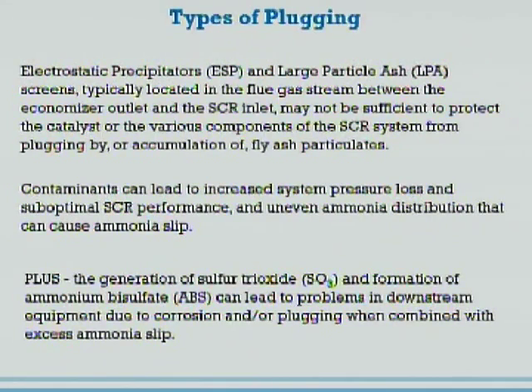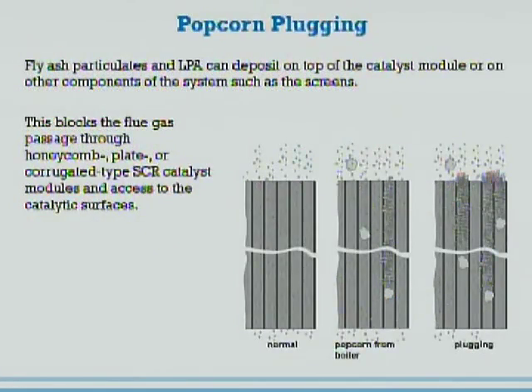But in spite of those things, a certain amount of fly ash tends to carry over, and in some cases quite a bit. Those contaminants can lead to an increase in several problems with your SCR, including system pressure loss, suboptimal performance, uneven ammonia distribution, and can cause ammonia slip. Anybody familiar with SCRs knows that ammonia slip when mixed with SO3 can lead to ammonium bisulfate buildup downstream, particularly on the air heaters. These are all problems we face when running SCRs.